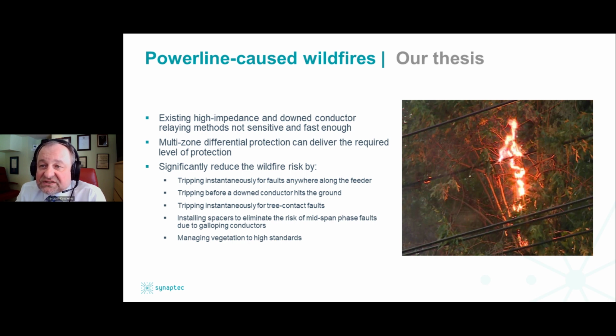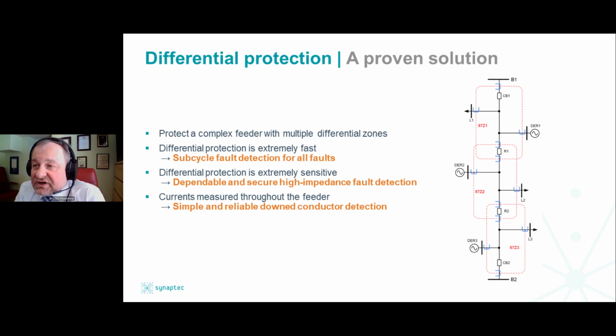So, for example, you will eliminate the risk of mid-span phase faults due to galloping conductors by using spacers. Those faults are really difficult to detect because before the time over current element times out, the fault is kind of gone, but it created energy that may result in a wildfire. And then, of course, managing vegetation to appropriate high standards. So differential protection is a proven solution.